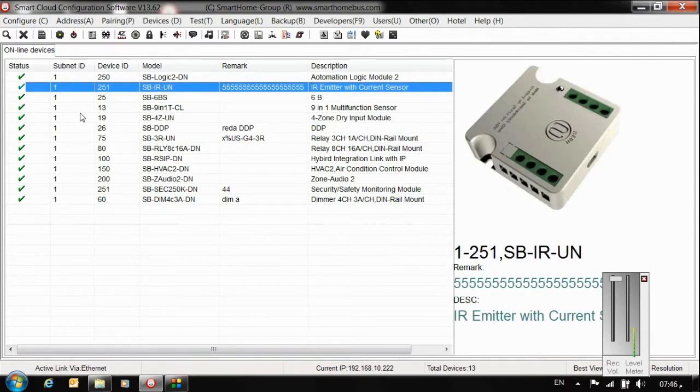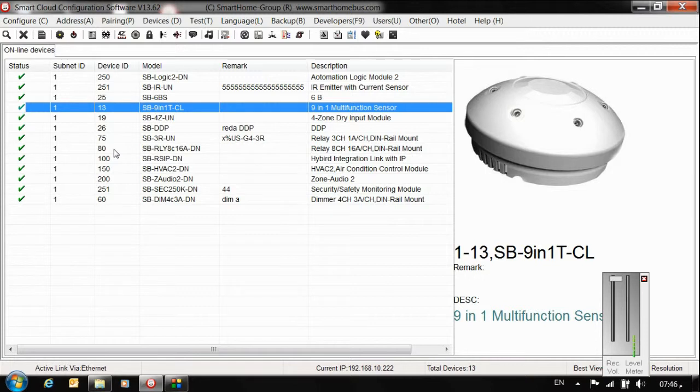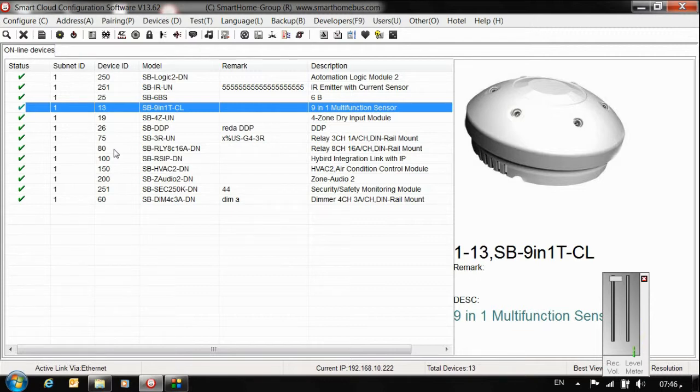In one subnet ID you can cover up to 254 devices, and at the same time you can cover up to 255 subnet IDs. That means the total is 65,000 devices, but usually in one villa, one subnet ID is enough - not more than 250 devices.